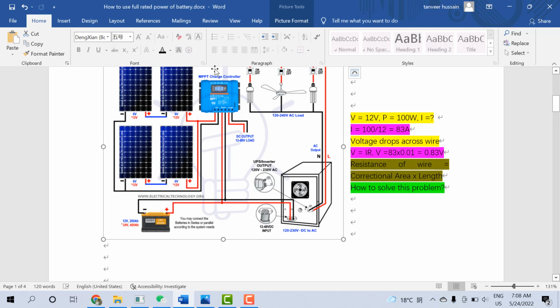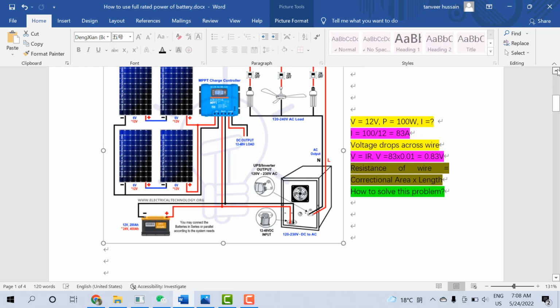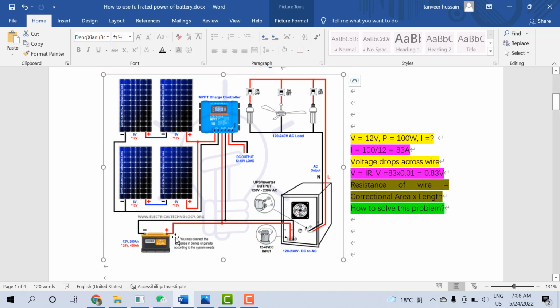You need to turn off the charger and turn off the inverter's power input only. Then turn on the loads, the maximum load you can, or at least 70% capacity of your system. When you turn this on, the battery will start discharging.